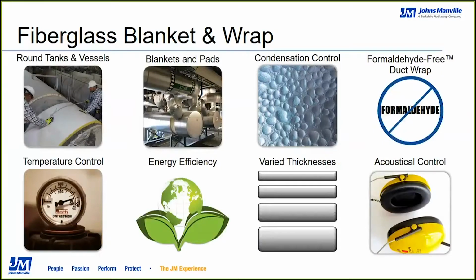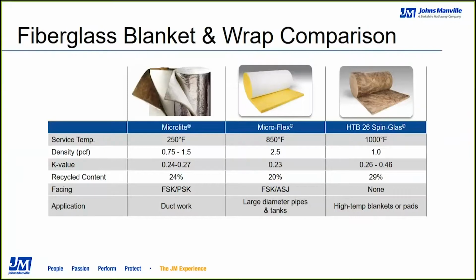Our duct wrap is formaldehyde free, and all of these products can also offer a certain amount of acoustical control. Microlite duct wrap is currently available with two facings, FSK and PSK, or polyscrim kraft. Again, going back and addressing those questions about can it be painted, that's really the birthplace of the white PSK wrap, for the aesthetic installations where the desire is to have the duct wrap appear white, either to blend in or stick out in a ceiling cavity or installation. Basically you have the two separate facings available. The product is also available in various densities, from 3/4 pound density up to 1.5 pounds. The K values will vary accordingly in regards to those densities, and again, you have varying thicknesses as well.